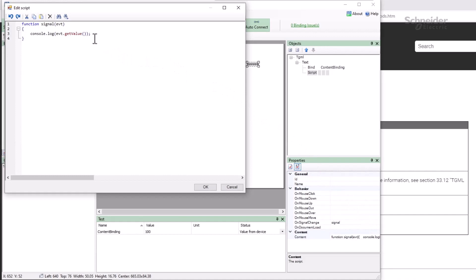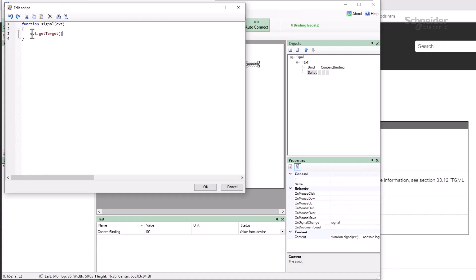The event object actually has two targets. evt.getTarget is the element that triggered the event. For a signal change, it's the binding whose value changed. For a mouse event, it's the element that was clicked or moved over. evt.getCurrentTarget, however, is always the parent element of the script itself.